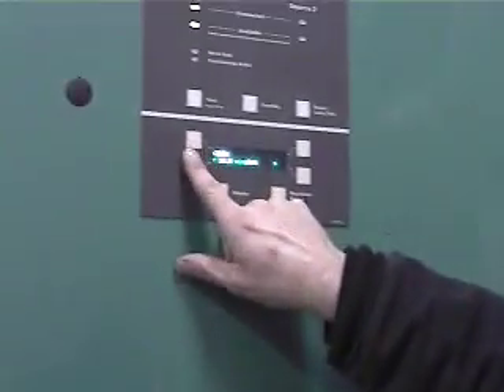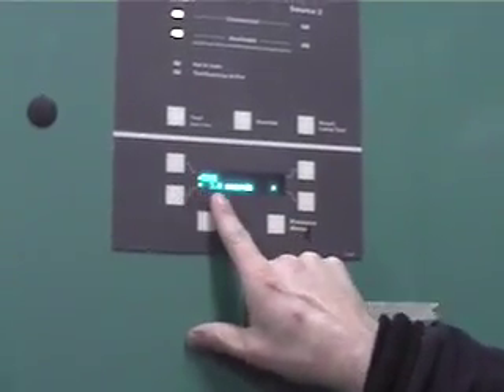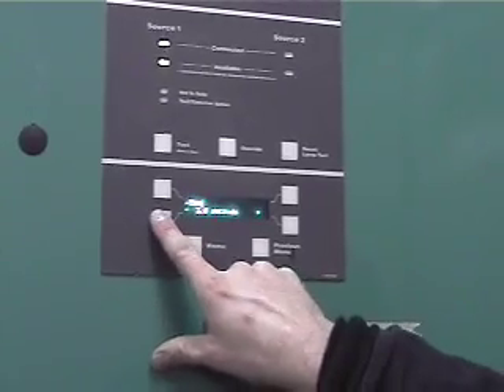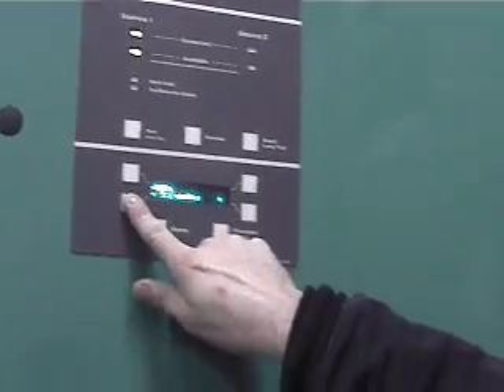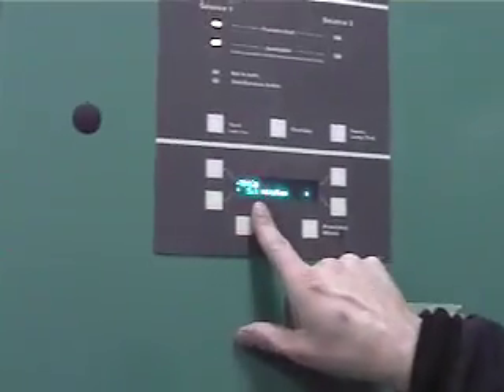So 3 seconds after power goes out, the generator's going to start cranking. Once it starts and comes up to speed, 3 seconds later it's going to transfer. This one I do have a program transition set for 3 seconds — that's the neutral time delay. So it'll transfer to neutral, sit there for 3 seconds, then transfer the rest of the way.